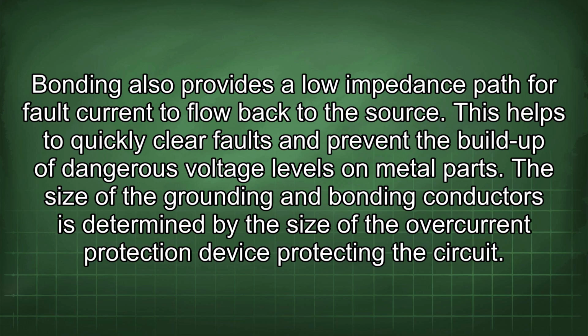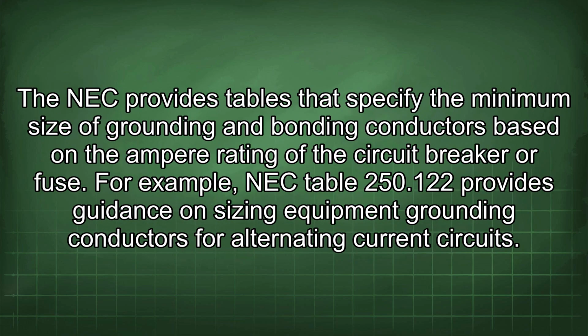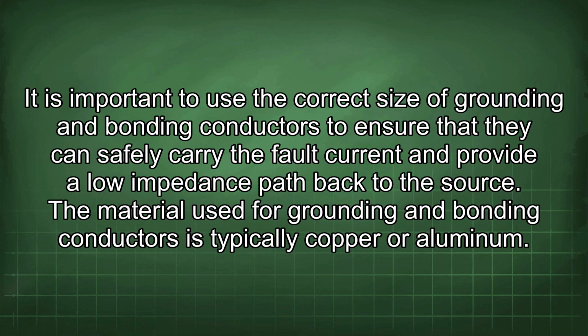The size of the grounding and bonding conductors is determined by the size of the overcurrent protection device protecting the circuit. The NEC provides tables that specify the minimum size of grounding and bonding conductors based on the ampere rating of the circuit breaker or fuse. For example, NEC Table 250.122 provides guidance on sizing equipment grounding conductors for alternating current circuits. It is important to use the correct size of grounding and bonding conductors to ensure that they can safely carry the fault current and provide a low impedance path back to the source.